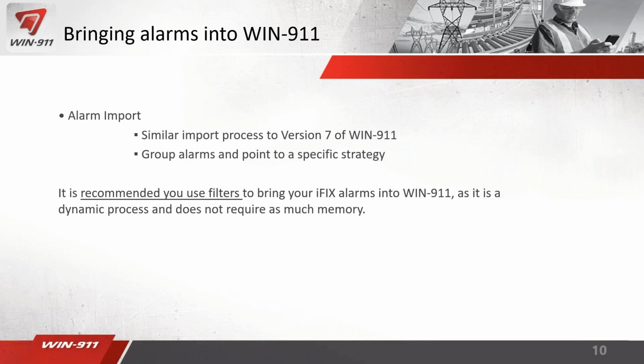They are dynamic and do not require a lot of memory, as opposed to using the import method, making your blocks one by one. That is a huge resource hog, and it takes a long time to initialize and get everything ready to actually start processing alarms if you have a lot of blocks. If you have just 100 or under, not a big deal, but once you start getting into multiple hundreds or even thousands, you're going to be waiting quite a while for things to be initialized.